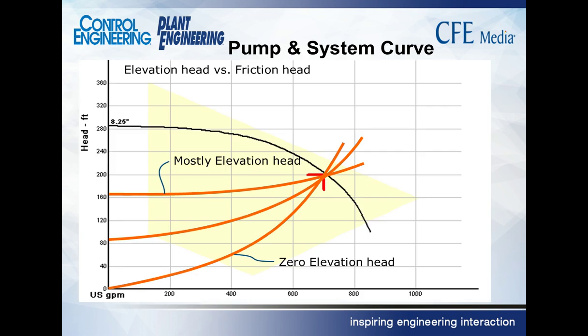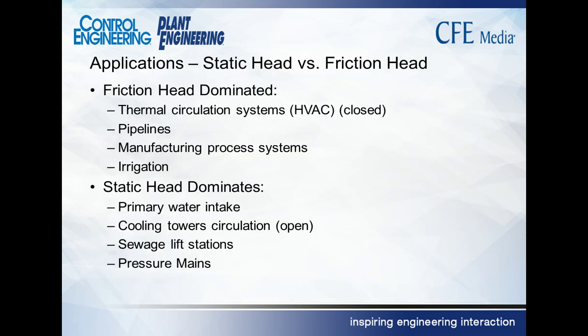So you can see the difference between the shape. The mostly elevation head applications have a very shallow system curve. The shallow system curve indicates high elevation. Look at zero flow. At zero flow, there's 160-some feet of head. We're not pumping any liquid through the system, and I still have to overcome the 160 feet of head because that's how high the discharge is away from the suction. And the zero elevation head system at zero flow has zero head. They don't move the liquid. There's no friction.